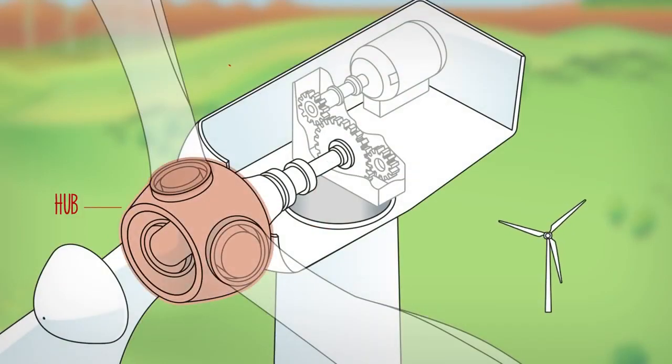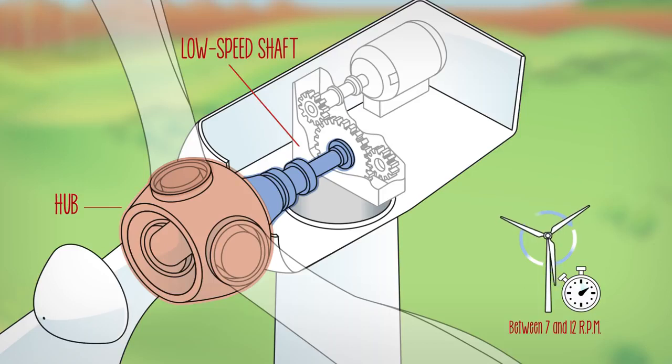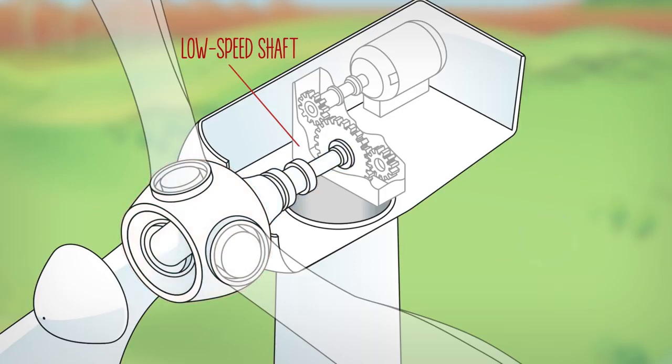The blades are attached to the wind turbine through the hub, which is coupled to the low speed shaft. The low speed shaft is given this name because it spins at the same speed of the blades, between 7 and 12 revolutions per minute. To produce electricity, it is necessary to increase the turning speed of the low speed shaft.